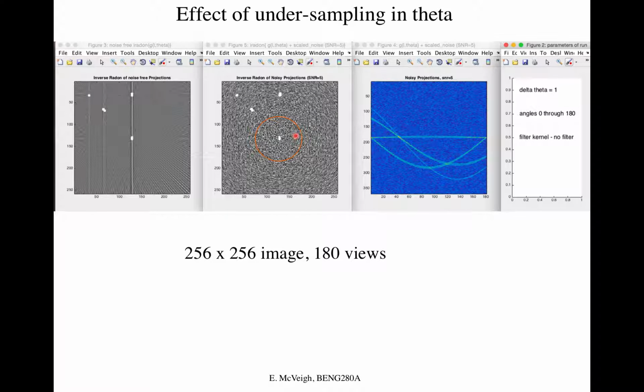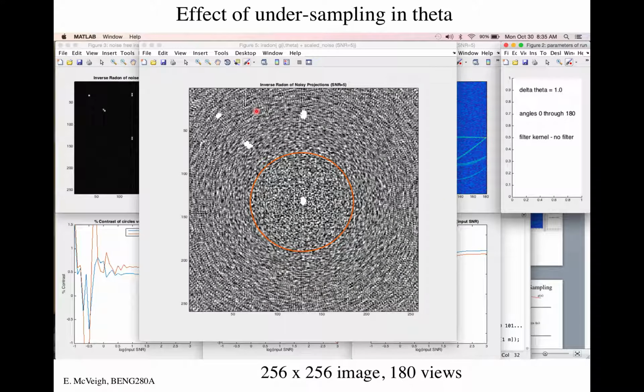Okay. So the question now is, what's going on inside this circle, inside which the noise field looks normal and the image looks like the correct resolution, and out here where I've still got some artifact and some blurring going on. So this is a 256 by 256 pixel image, right? And it has been reconstructed using 180 degrees or 180 projections, right? And so they're 1 degree apart through 180 degrees.